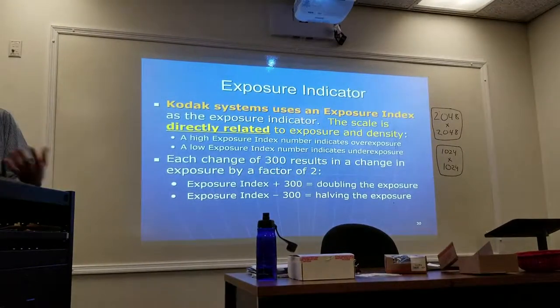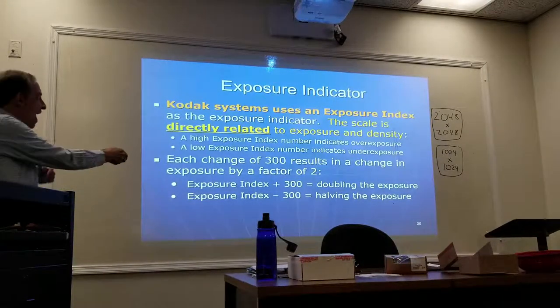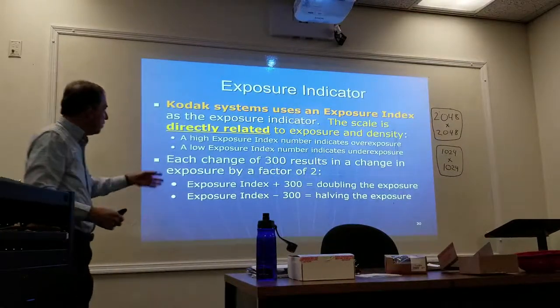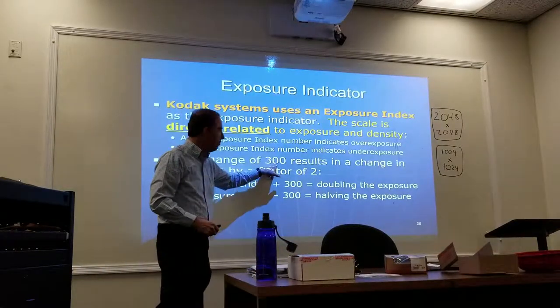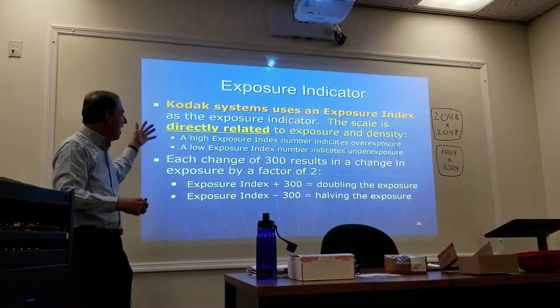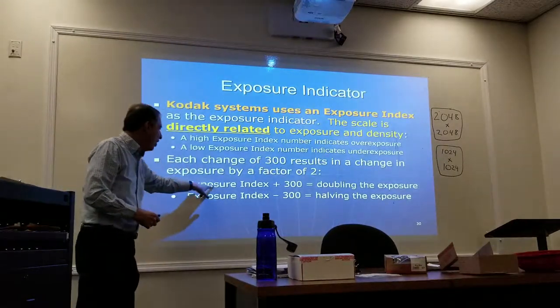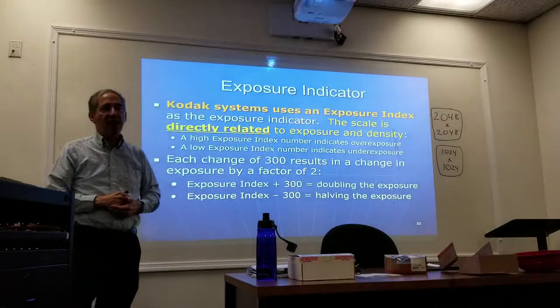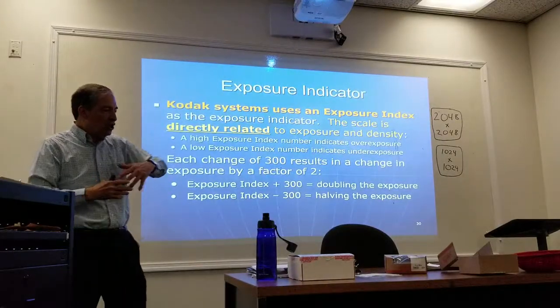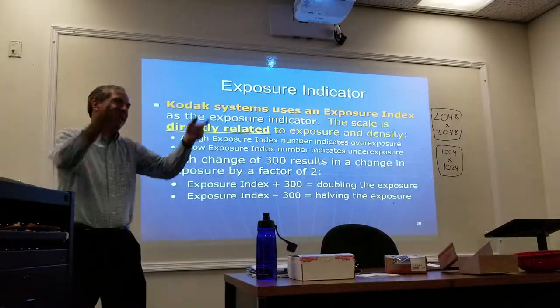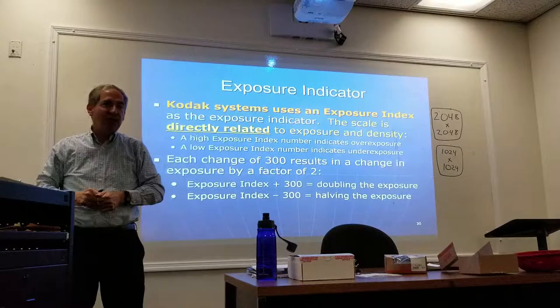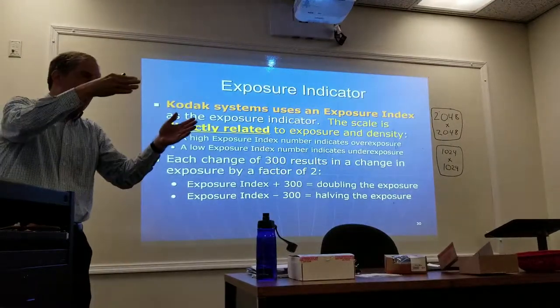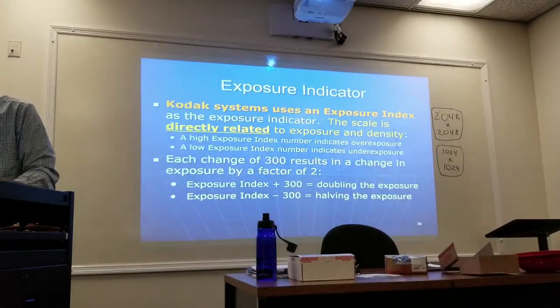Kodak uses an Exposure Index, which is directly proportional to exposure density — a high Exposure Index means overexposure, a low one means underexposure. Here the change needed is 300: adding 300 to the Exposure Index is the equivalent of doubling it, subtracting 300 is the equivalent of halving it. Sometimes an image is so far out that you have to go through a couple of steps — it's four times as much, not just doubled.